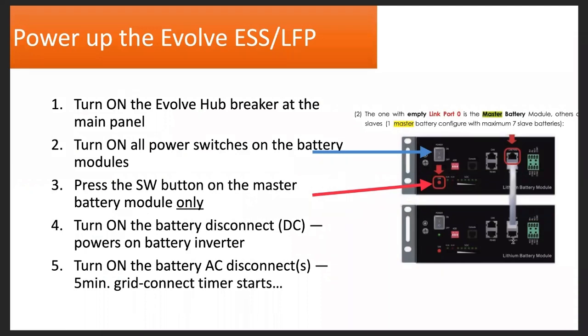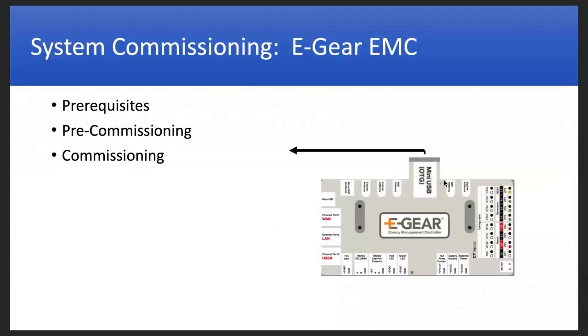So then at that point, you would turn on the battery modules with these toggle switches, and then press the SW button on the master module, and that'll power on all of the modules in the rack. Once the DC side is on, just like with a string inverter, DC first and then the AC. Once it's powered up, it has a grid voltage timer, a standard IEEE timer, 5 minutes, and the battery will then grid connect. Once it's connected, then you would commission the system.